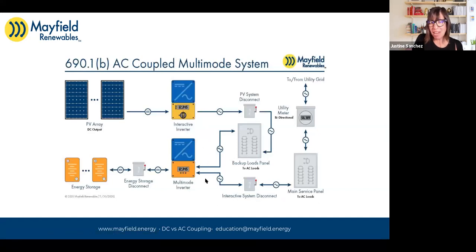However, you'd have to have some kind of bypass switch, because remember, if you pull this box out, depending on its pathway to route the power back over to your main AC service panel, you'd need a bypass switch to do that with. So it's not just assumed you have this redundancy. It depends on how you've actually designed and installed the system. Because if this pathway is dependent upon this multi-mode inverter and that thing is out for repair or gone, then you don't have that pathway.